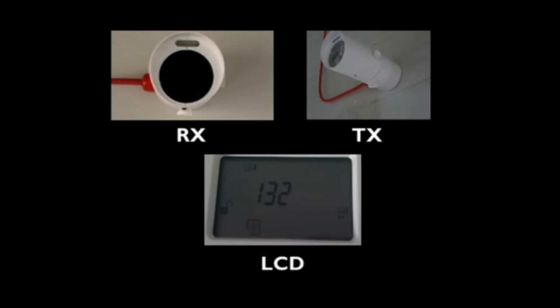When the LED flashes amber, or the alignment value starts to decrease, the transmitter has been moved past the point of best alignment in that axis. Rotate back 1/8 of a turn, or so that the LCD alignment value returns to its highest seen value. Alignment in this axis is completed. Now adjust the other thumb wheel using the same steps as for the first thumb wheel.